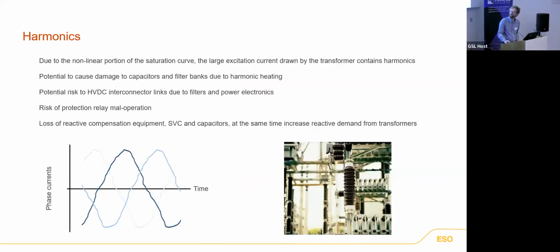Sorry about this. I think it's, oh, there we go. So back to the curve within the transformer, because we're now operating outside the linear portion of the transformer's capability, into the non-linear portion of the saturation curve. A large excitation current drawn by the transformer, so the current required for that magnetic field contains harmonics. In other words, it's a noisy signal.